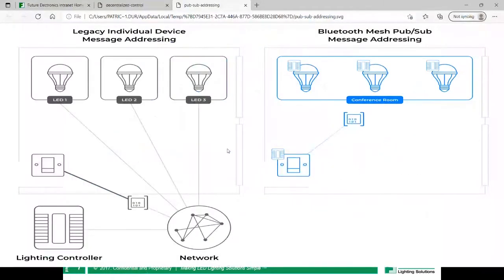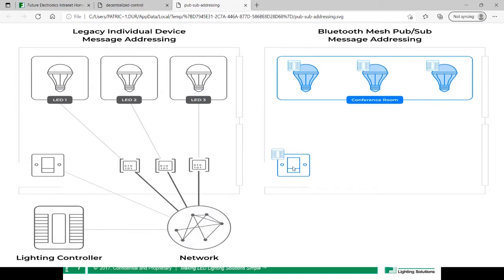Next is publish and subscribe. From a Zigbee standpoint, the gateway needs to be smart enough to handle this. But with Bluetooth mesh, if you define a zone or group address called conference room, the switch publishes to conference room, and all luminaires in that zone read and react to the message — making it super simple. As you add more devices to conference room, they automatically read the messages from the switch, enabling simple, low-cost installations.